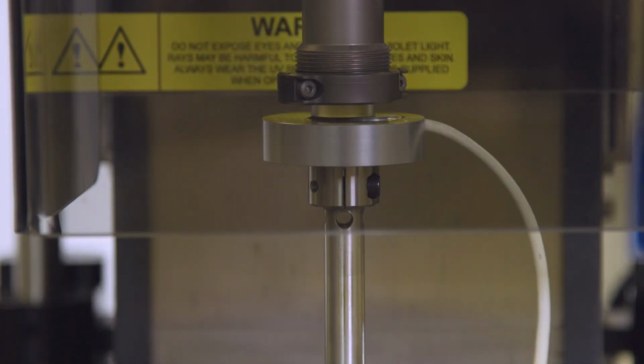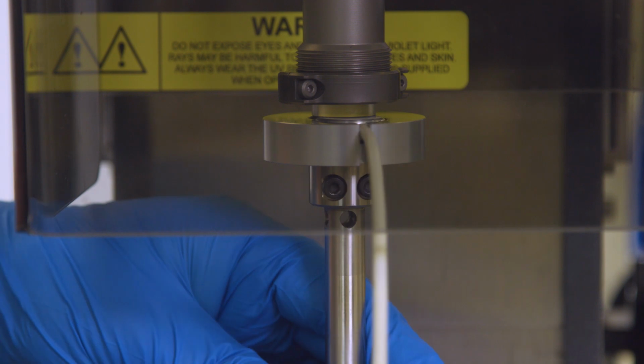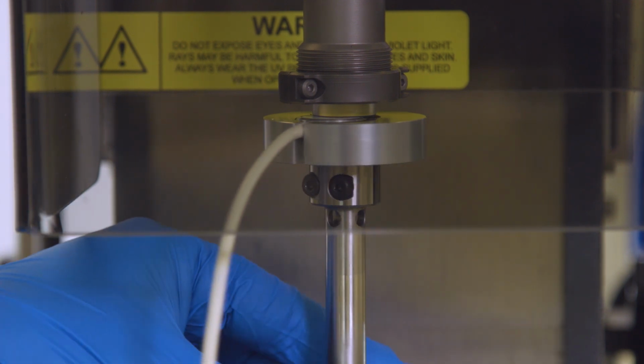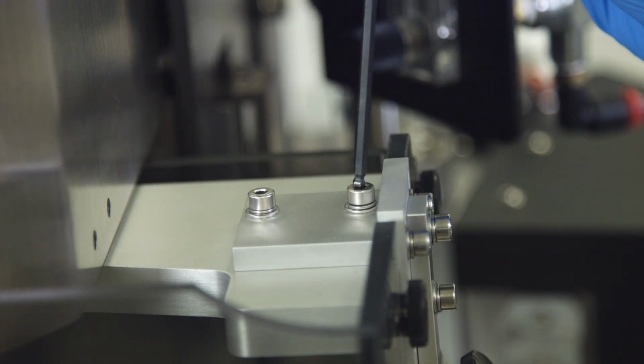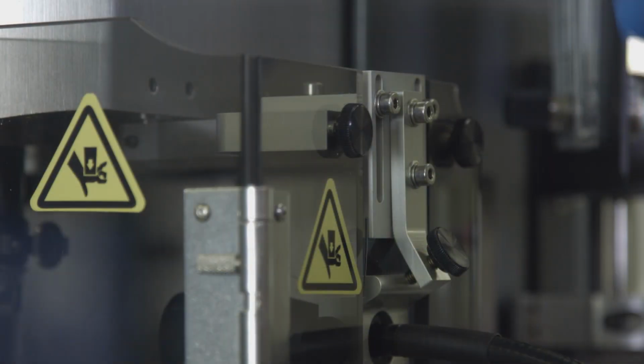Rotate the lower geometry to make sure the light is the same intensity at 4 locations that are 90 degrees from each other.